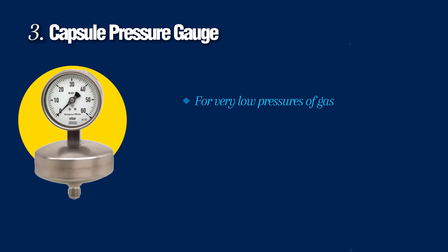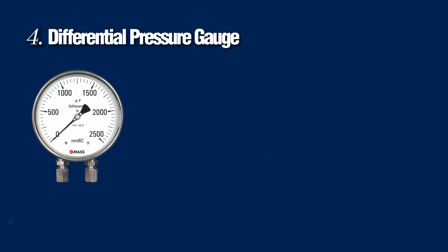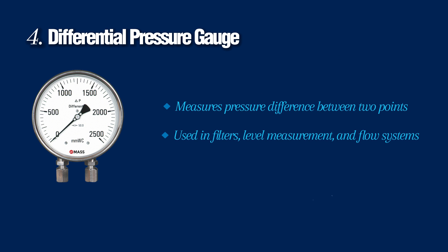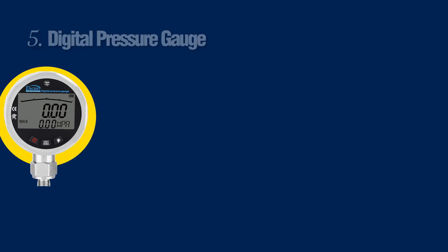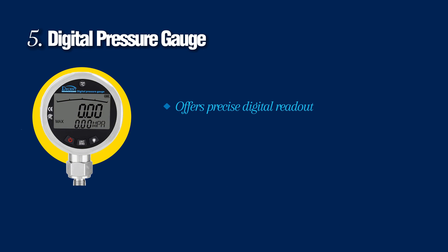The third one is the capsule pressure gauge, used for very low pressure of gas and in clean room or HVAC applications. The fourth one is the differential pressure gauge — it measures the pressure difference between two points and is used in filters, level measurement, and flow systems. The fifth one is the digital pressure gauge, which offers a precise digital readout and comes with memory, alarms, or wireless options.